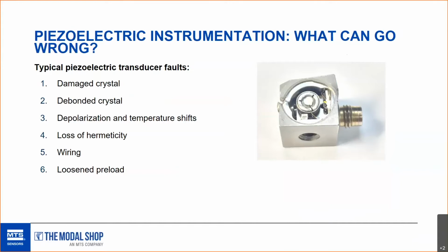An ICP sensor has a bias voltage, something you'd find on an electric motor, which is a nice red light, green light for your signal conditioning to show that the sensor is working. But when charge accelerometers completely die, they just fail to produce an output. There's no bias voltage. Usually you can catch it because you'll have an unusually low vibration or pressure level. But if you normally have noise in your signals, that can be missed. Or if you normally run really smooth and expect a low vibration level, it could be missed, but you'll probably catch it if it flat out dies.